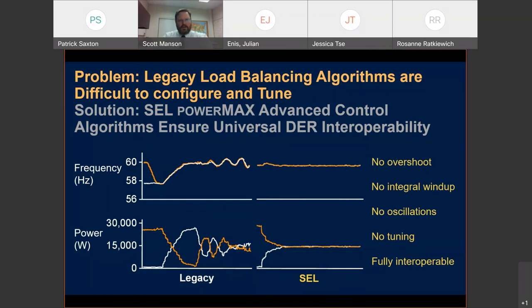And these systems have no significant overshoot. They have no PID, so they're not going to have integral windup. There's no tuning. There's no oscillations. It goes right to set point because it knows exactly where to go. Okay, that's getting your physics right.